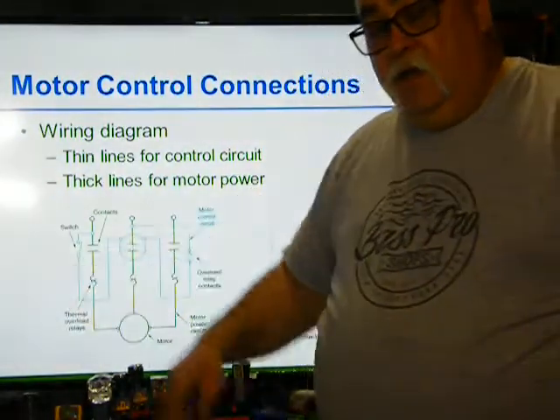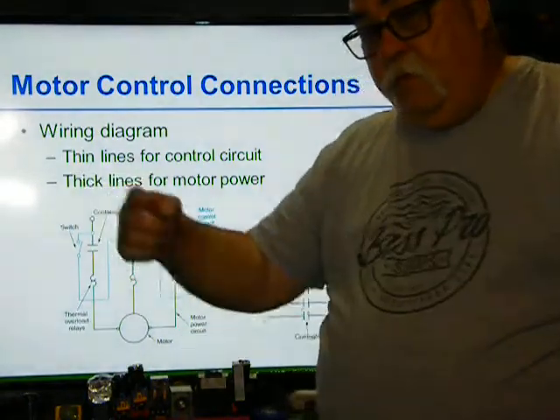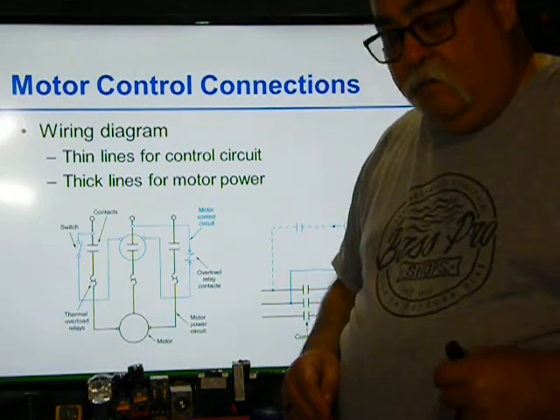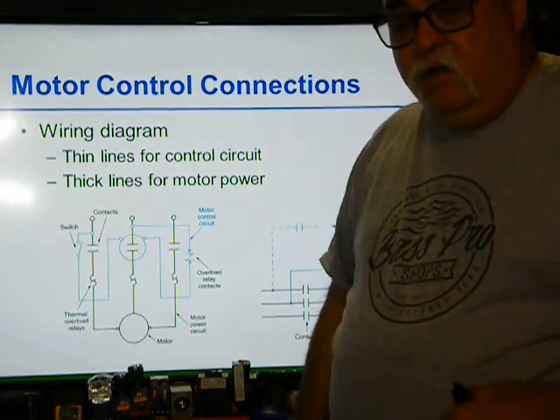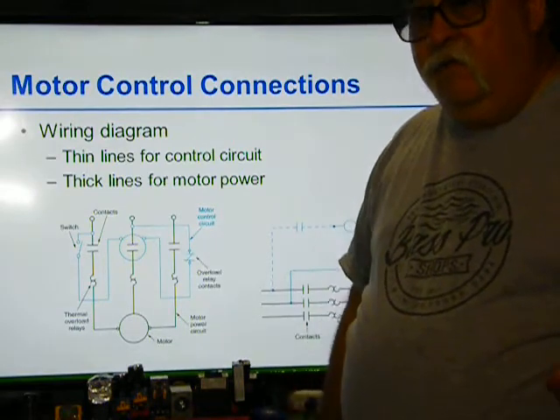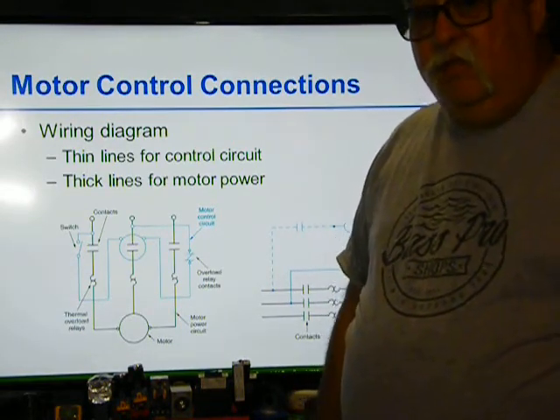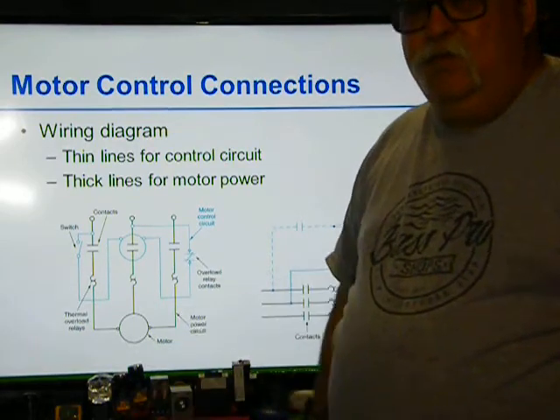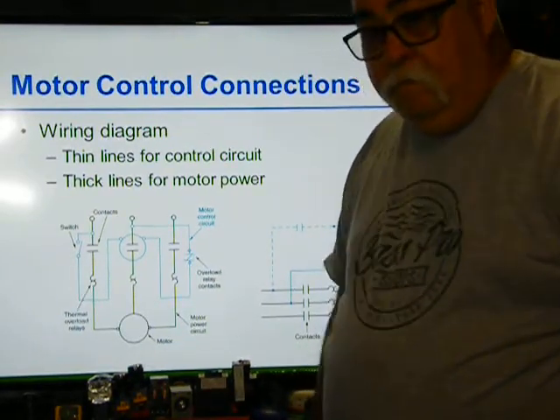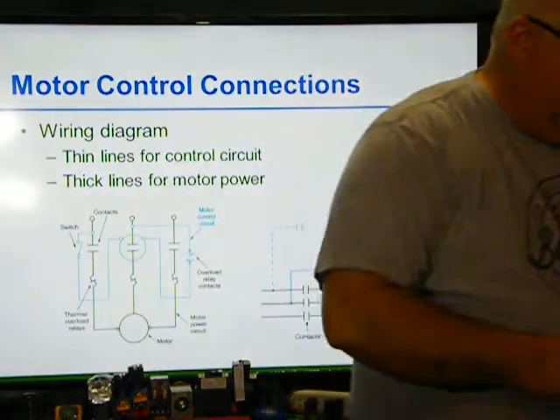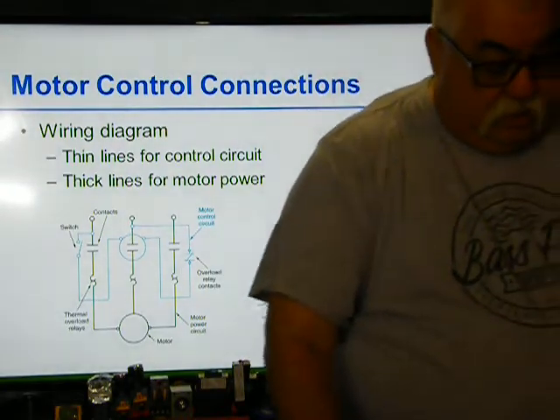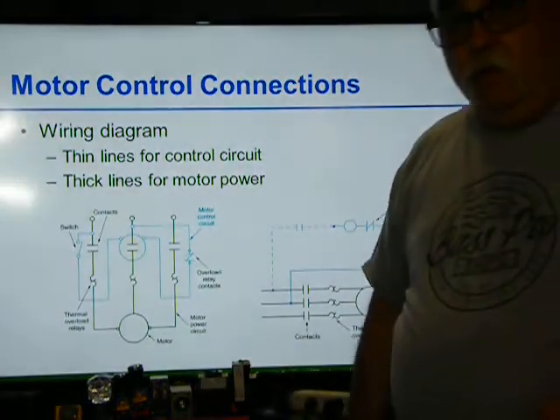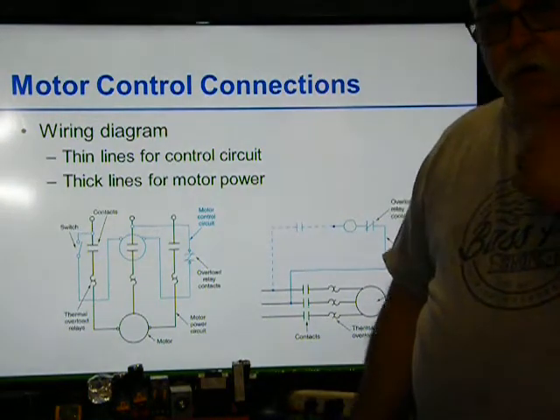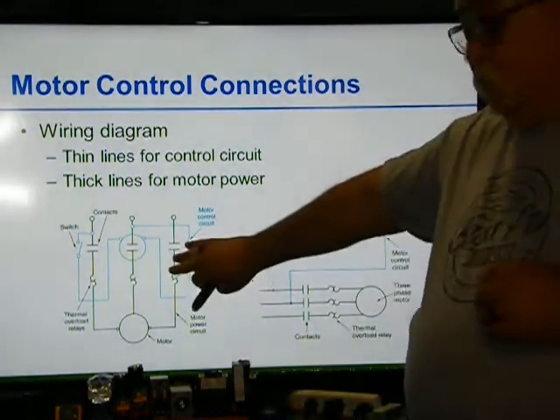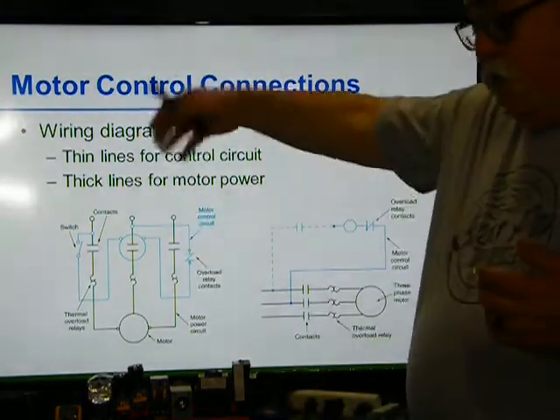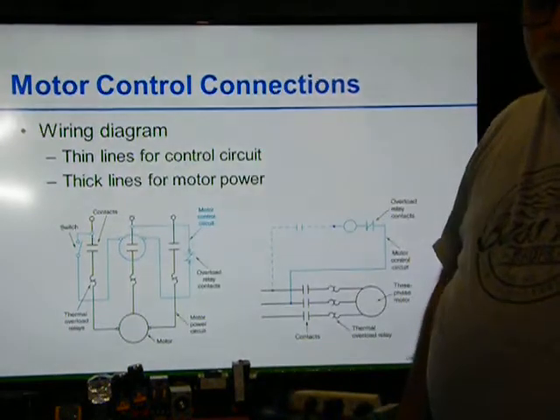So we can come off of this with our 2 hots and go to the transformer, with a primary side fuse and a secondary side fuse. Now we can knock it down to 120 volts, 115 volts, or 36, 48, 24, whatever voltage you need. That's all you need, because they do make them in 36. We have one motor starter in the class that's a 36 volt coil. For the most part, 120. I do have one starter that's a 220 volt coil. In that case, I wouldn't need a transformer. If my applied voltage is 240 volts, I can use the coil that's already inside of it.